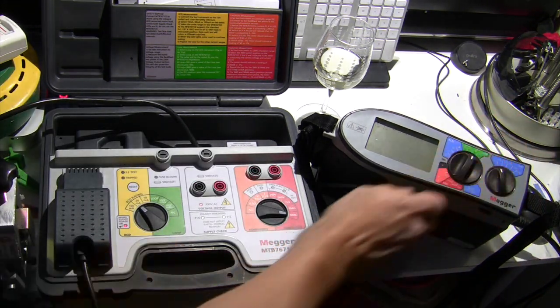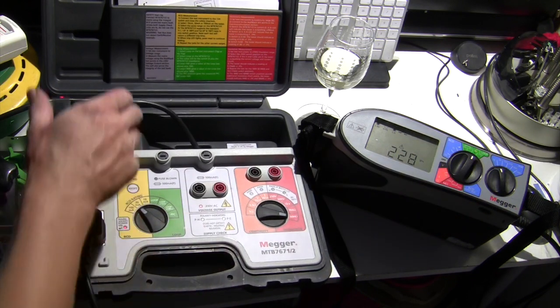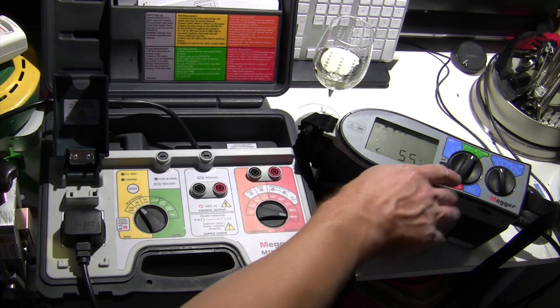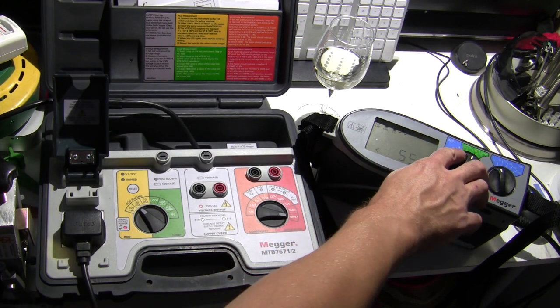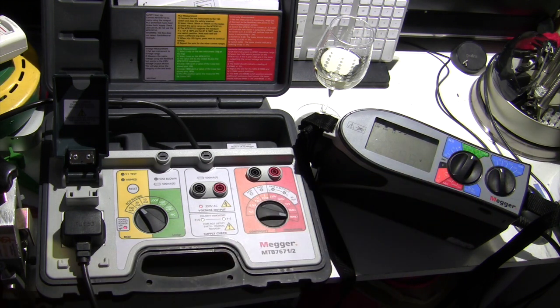So I'm going to switch this to high loop. Now the loop on the... oh crikey, don't go yet. On the Megger here, the loop functions are on the green side of the dial, and there are 4 settings. On the right hand side we have high loop and high PFC, so this will do your earth fault loop impedance and your prospective fault current on a circuit that has no RCD, and give you the numbers for that.